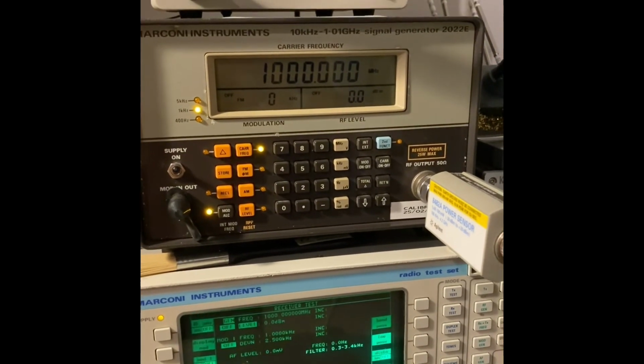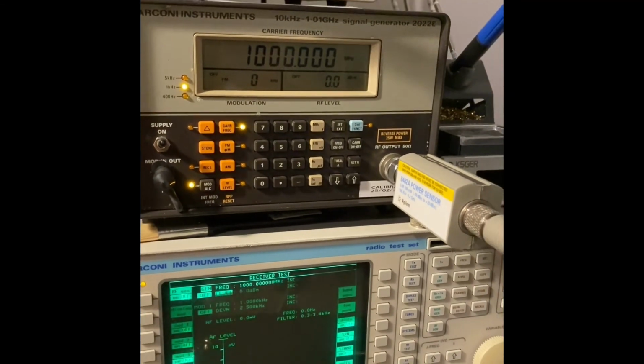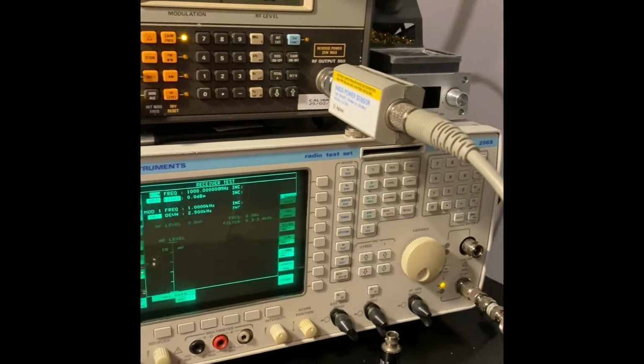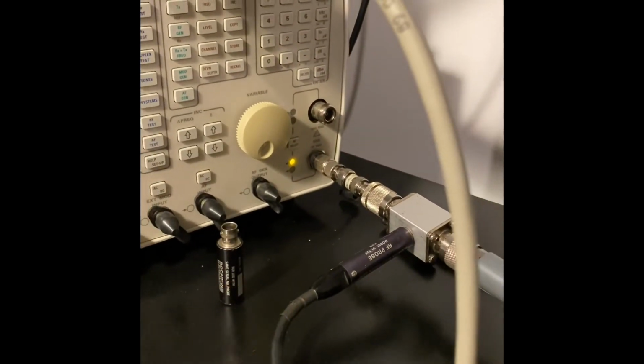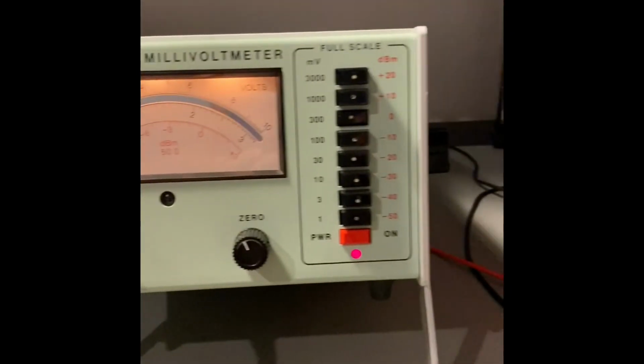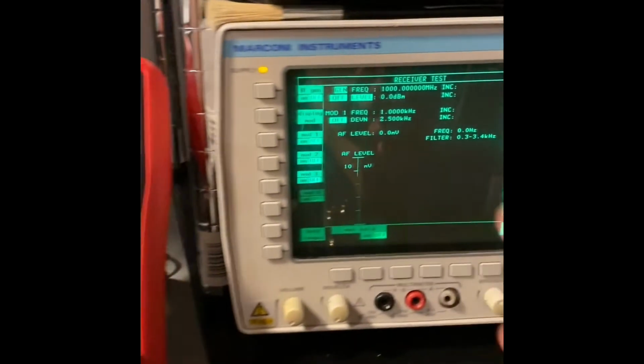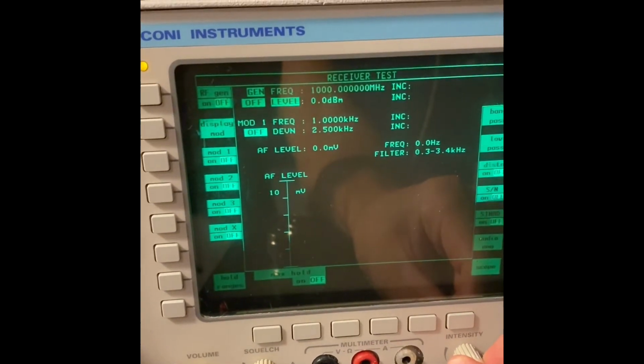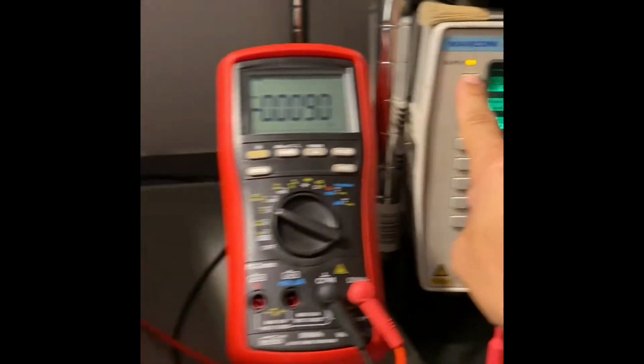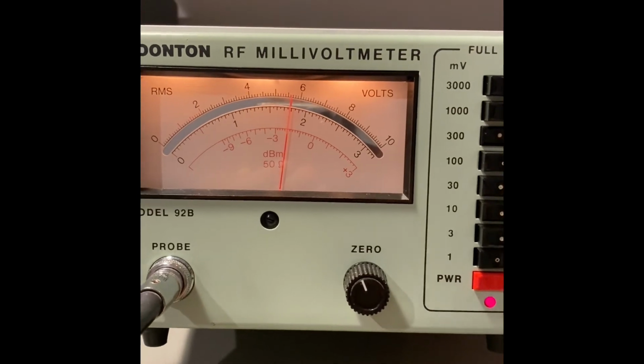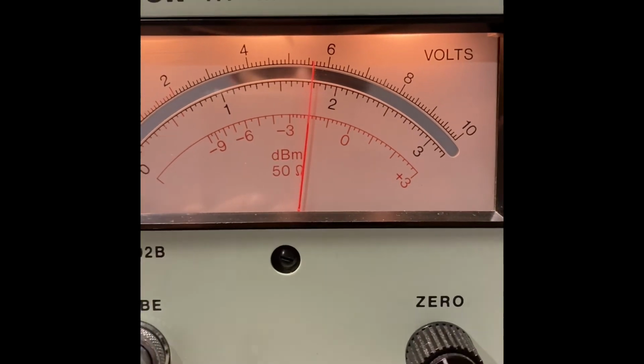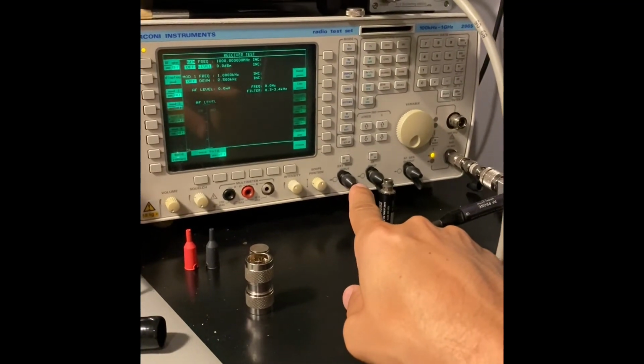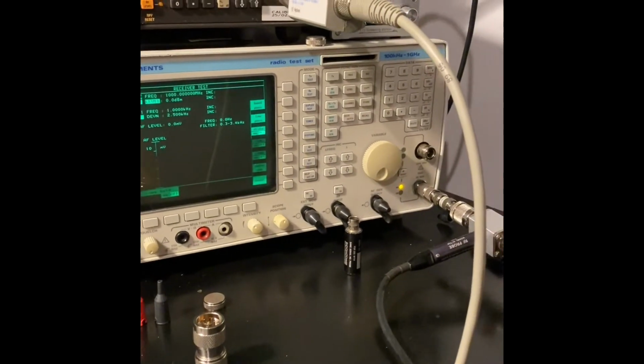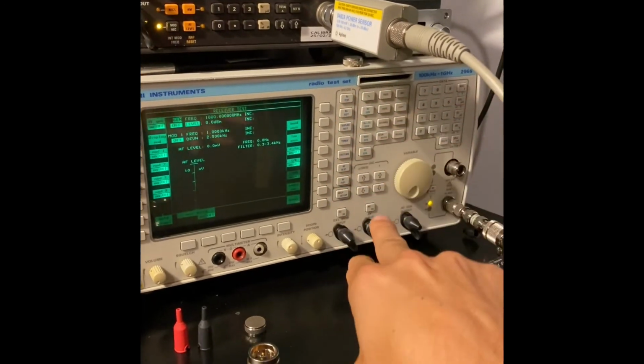So 0.2. So let's see what the power sensor thinks about the test set. The test set now is hooked up to the BOONTON probe, so we could actually check the BOONTON reading at 0 dBm, 1 gig. So RF gen on, 0 dBm, and it goes to -2. But I know that this test set is not very linear with frequency. Going up and up to the edge, it drops the level a bit. So we now check the test set with the power sensor, and we go back with the BOONTON probe to the 2022.